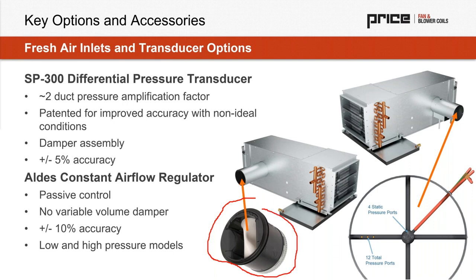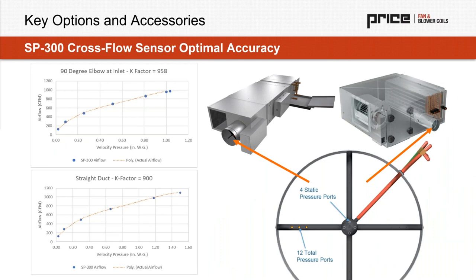This is the Aldes CAR, which is an option from Price for passive control, no motorized actuator, and plus or minus 10% accuracy. Or we could have a variable volume, higher accuracy solution in the Price SP300 Crossflow. There are many products that look like this in market, and ours is actually patented, and it's patented specifically for improved accuracy with non-ideal conditions. This is going to amplify duct pressure, allow for a more resilient pressure signal, and it's going to work even if we have bad inlet conditions.